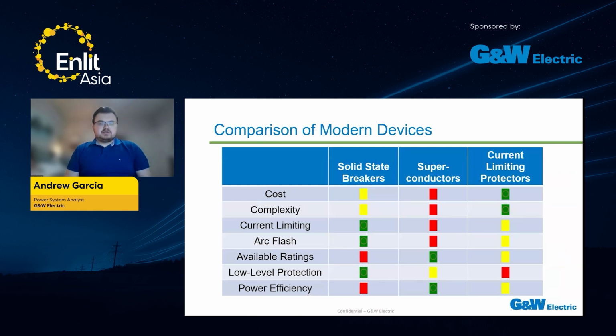So how do these stack up together? If you have a project where your traditional devices aren't sufficient or come with severe drawbacks, and you're going to consider some modern devices, how do these exactly stack up? In terms of cost, they're all going to be pretty costly, but from least to most costly, current limiting protectors are definitely going to be a bit less expensive than solid state breakers and superconductors, just due to it being a more mature technology. The solid state breakers are very interesting as well. Once again, with superconductors, you need to lay a long length of very expensive superconducting material in order for that to function.